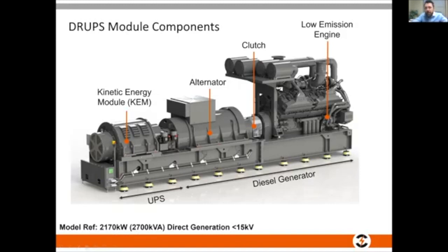This diesel generator is probably 20 feet. And it's the same size diesel generator, whether you were to buy a 2.2 megawatt generator from MTU or Cummins. It's the same size. It's the same components. But what I've done is added this flywheel, which is about 5.5 foot. So now my 2.2 megawatt UPS is within the density of this 5.5 foot machine. Maybe the disadvantage of Drups is that it is mechanically coupled, so I can't put this flywheel somewhere else. So I do, by virtue, increase the size of the diesel generator if you see that as a disadvantage. But of course, the amount of footprint squared is significantly smaller.